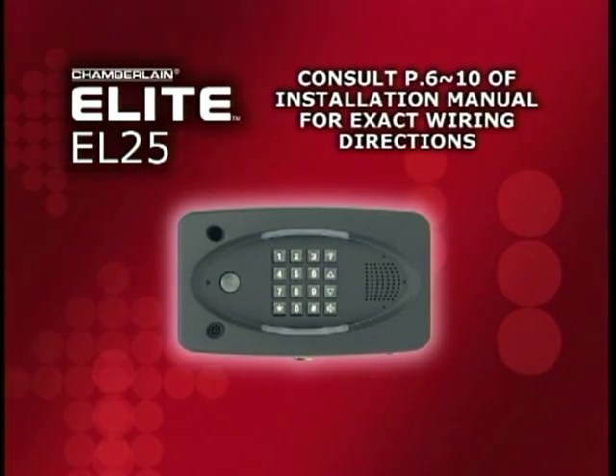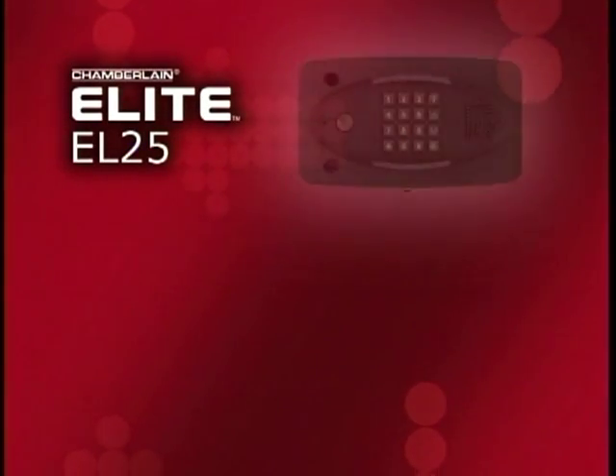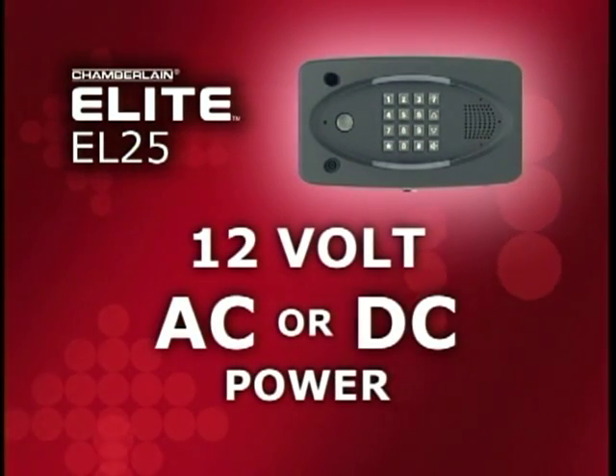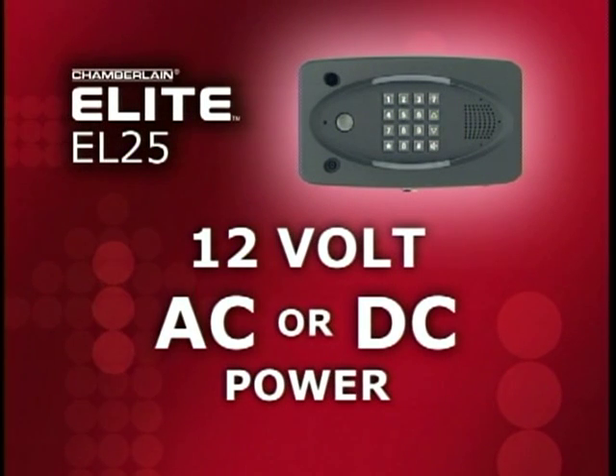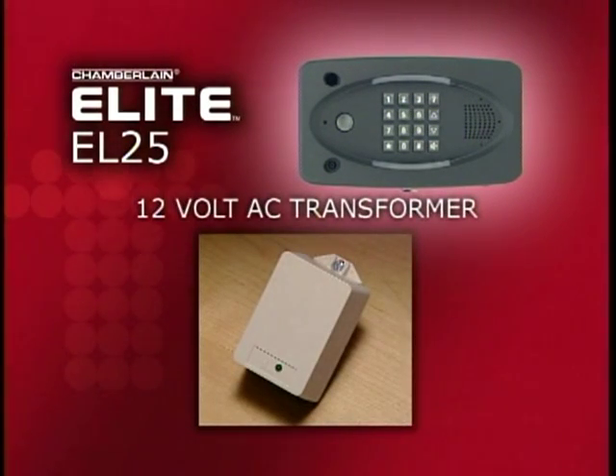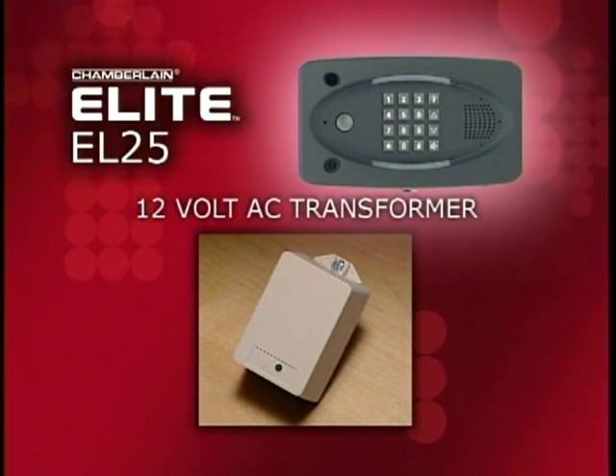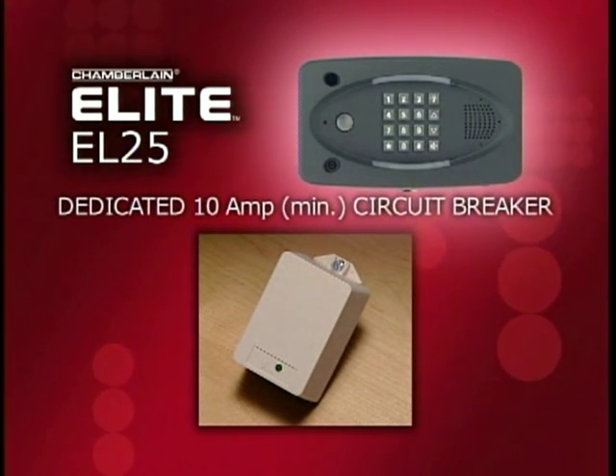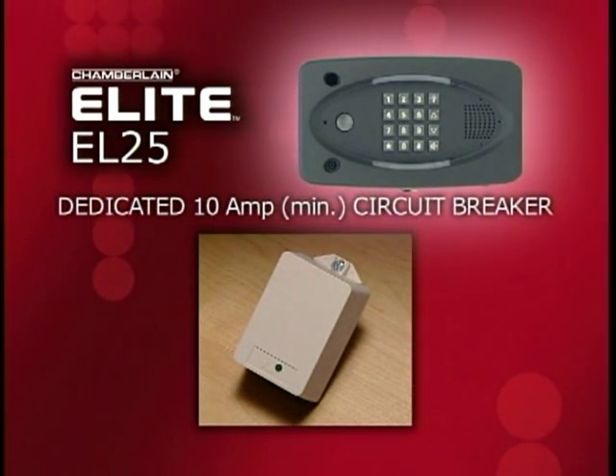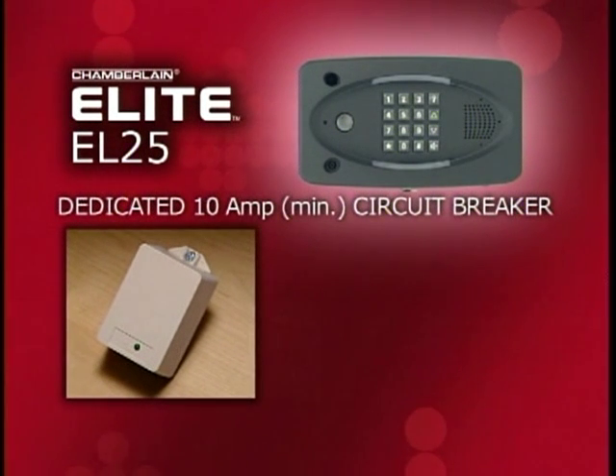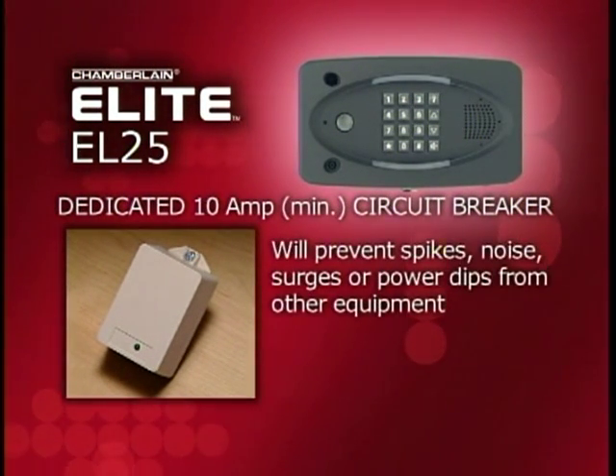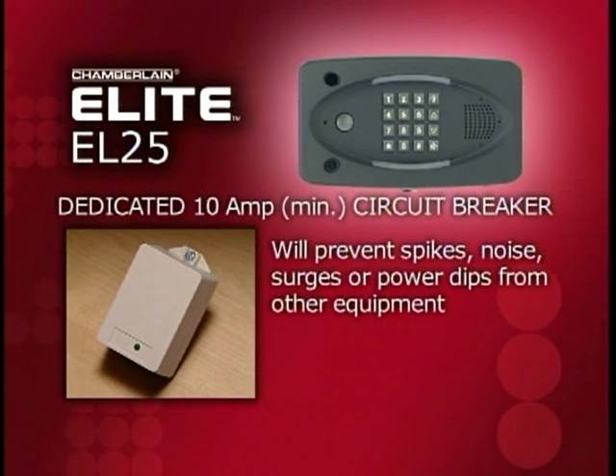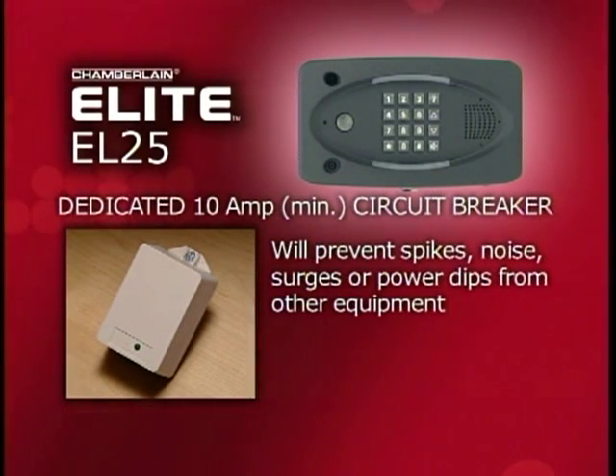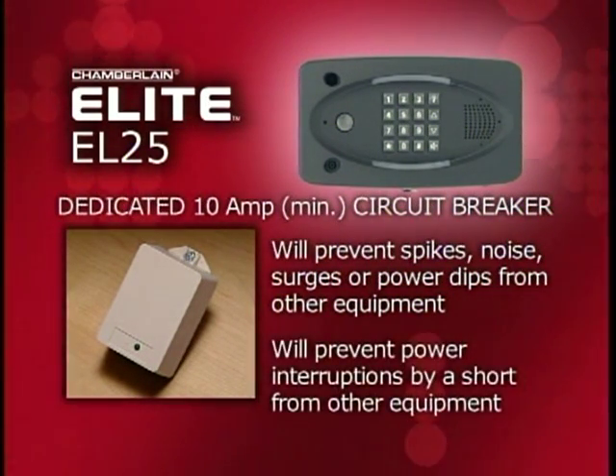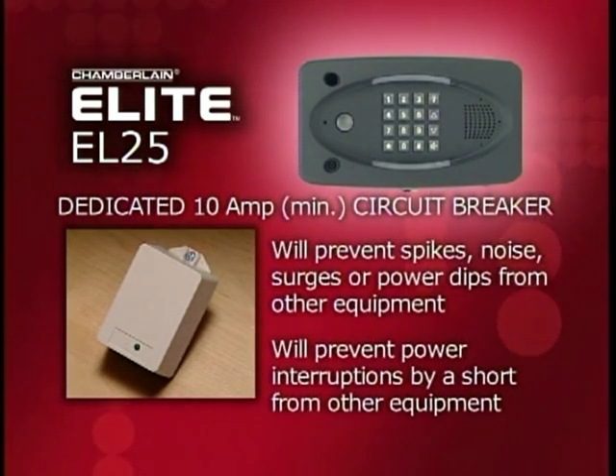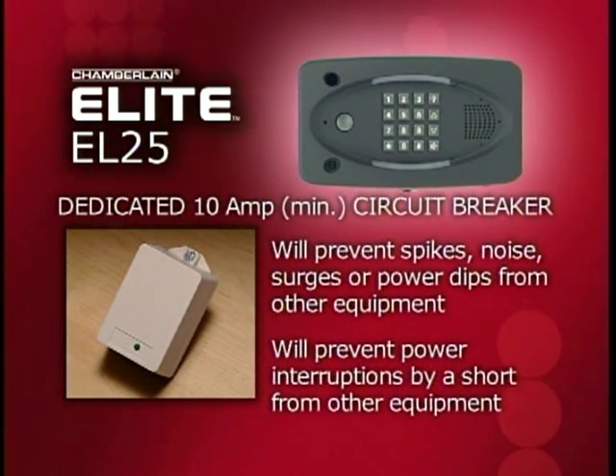The EL25 operates with 12-volt AC or DC power. A 12-volt AC transformer is provided. It is highly recommended that a dedicated 10-amp minimum circuit breaker be provided for powering the EL25. This will prevent 2 potential problems. First, other equipment on the same power line could introduce spikes, noise, surges, or power dips. And second, the system's power will not be interrupted by a possible short in another piece of equipment on the same line. Review the wire chart in the installation manual for proper wire size and length.